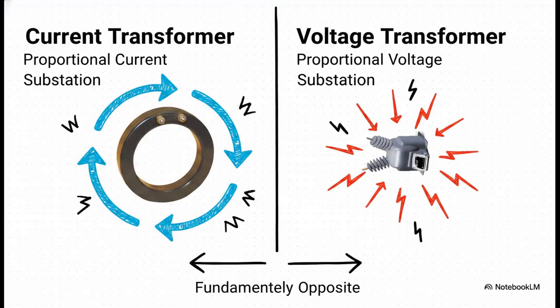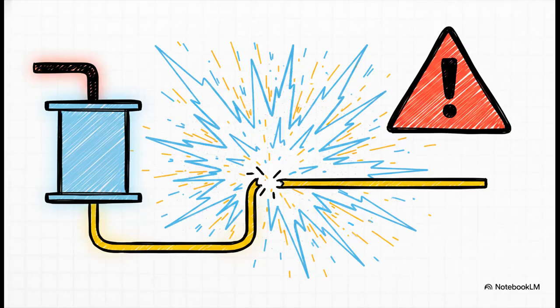Before I drop these rapid-fire safety rules on you, just notice the stark visual contrast between these devices. We have a current transformer, which is a proportional current device, and a voltage transformer, which is a proportional voltage device. Now, they might look somewhat similar to the untrained eye, and sure, they sit in the same substations, but physically, they operate on fundamentally opposite electrical principles. Which brings us right to rule number 1.